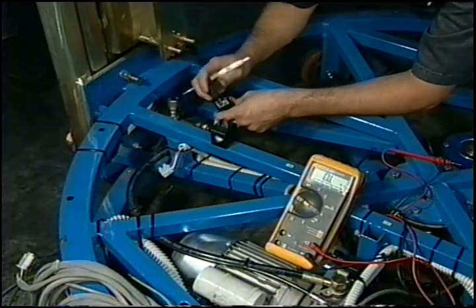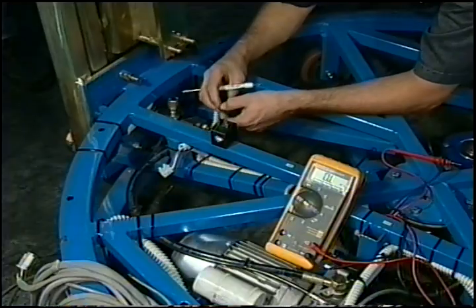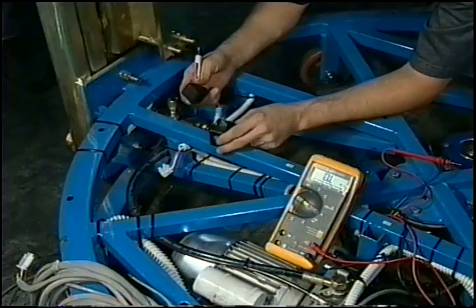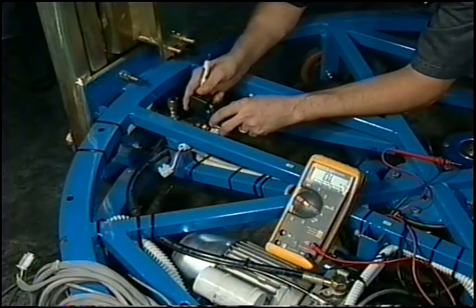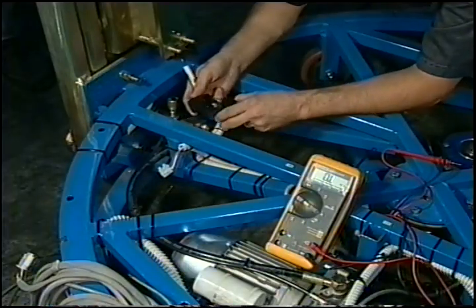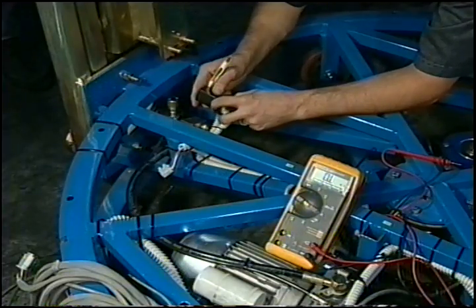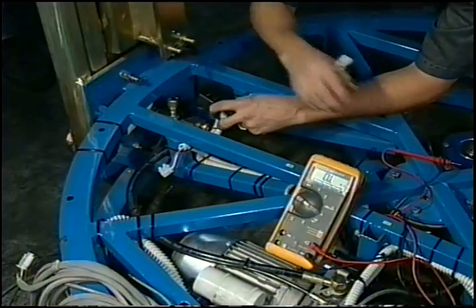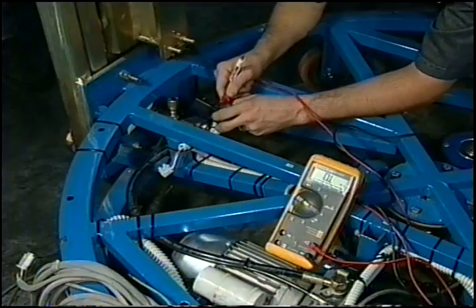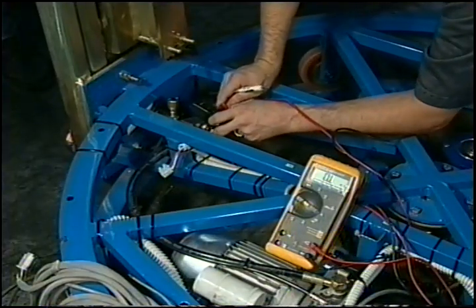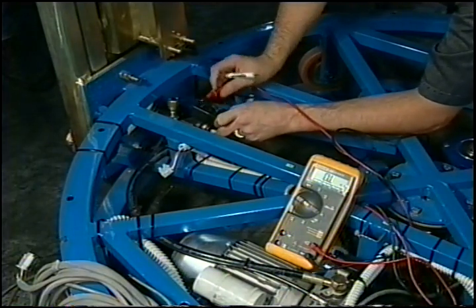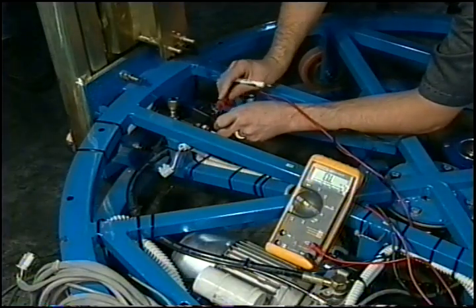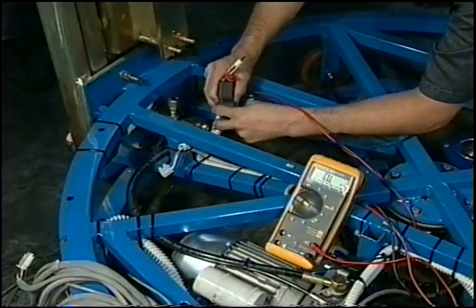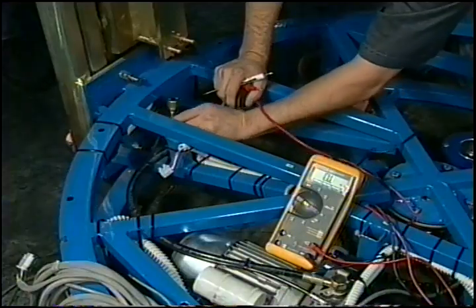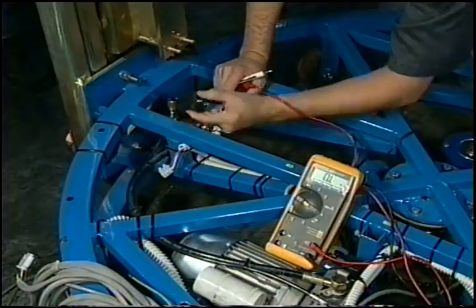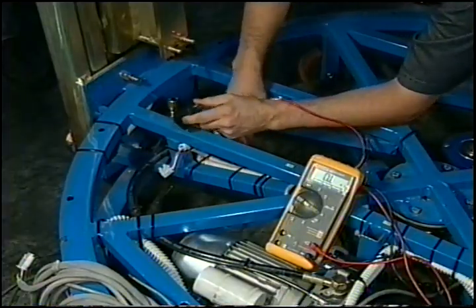If you find that that's gone bad, you just get a replacement from the parts department. But if you also wanted to check this, your meter leads won't fit into the holes. So what you can do is stick the part partially in there, leaving yourself just enough room to get your meter leads in to where you're making contact to the pins. And you should read anywhere from 90 to 100 volts DC, because your bridge rectifier circuit is breaking down that 110 to a DC voltage. When you're all done, you just slip it all back on. Many times when this does fail, it's just the coil that's failed and not the valve itself. So you can just replace this and generally get your ride going again.